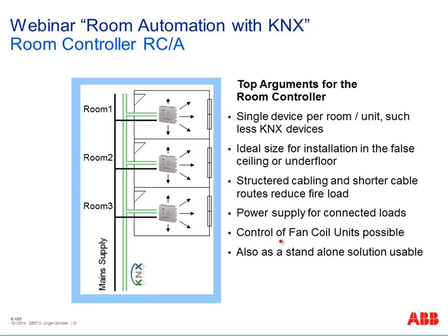If you want, you can use such a room controller also as a standalone solution. What does it mean? You have inserted your modules with inputs and outputs. Temporarily, you need, of course, a KNX system behind to program inputs and outputs with each other, to connect everything with each other. And then you can disconnect KNX, and with the power supply of the device itself, it works as a standalone solution. And of course, all loads are also connected.